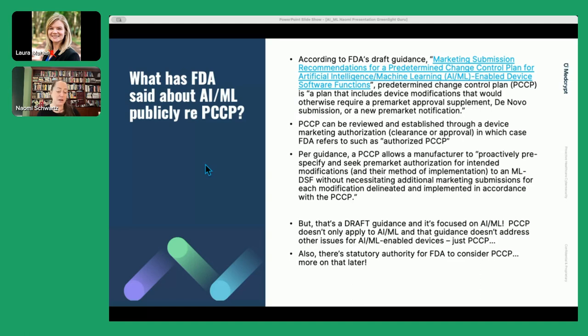It is also great because it means FDA reviewers don't need to review all of the changes. If you have a Class 3 device and a pre-market approval, you don't need as many PMA supplements. That is fantastic for both you and your review team. They will be delighted to not have 35 PMA supplements in a given year because you're making some changes to your AI or machine learning enabled software functions in a device.